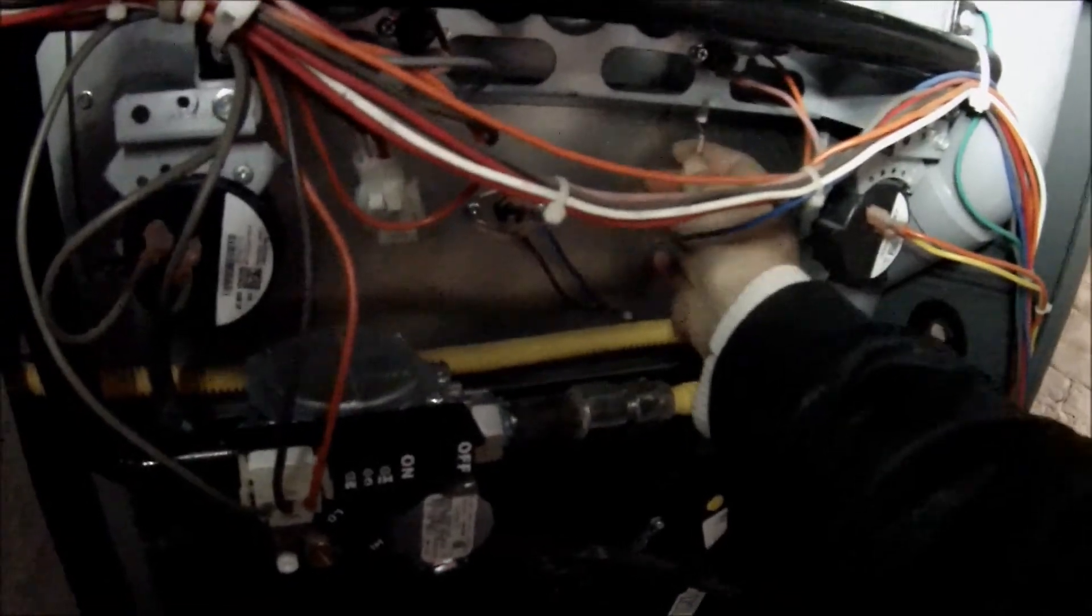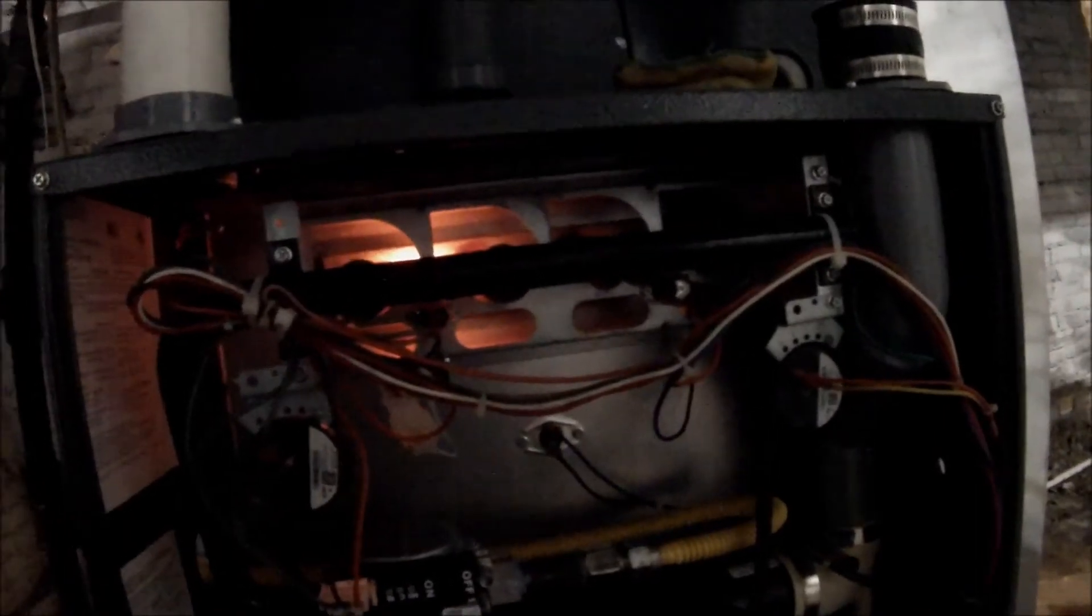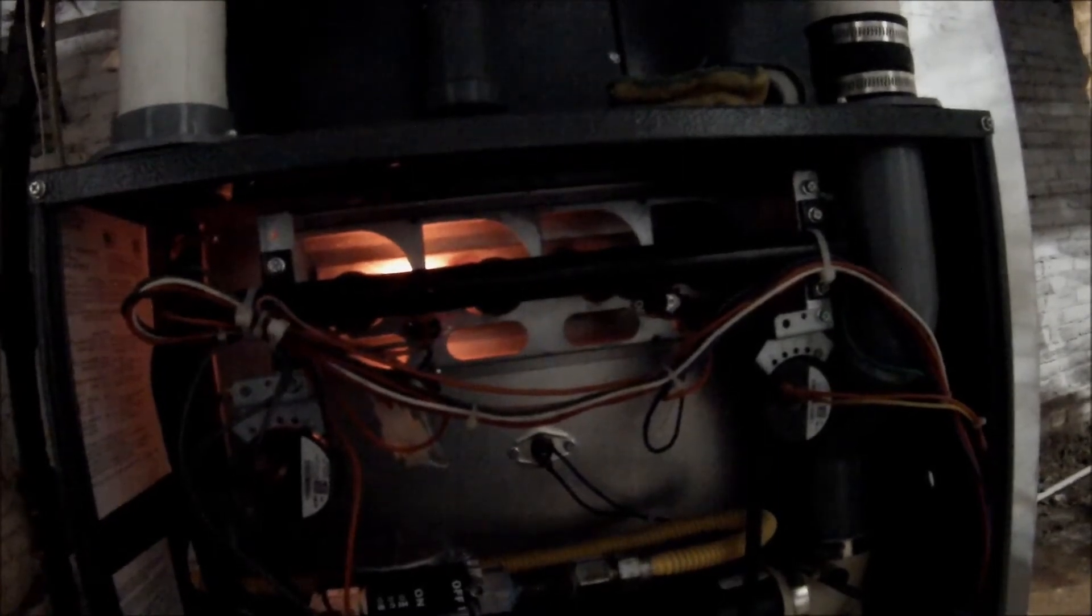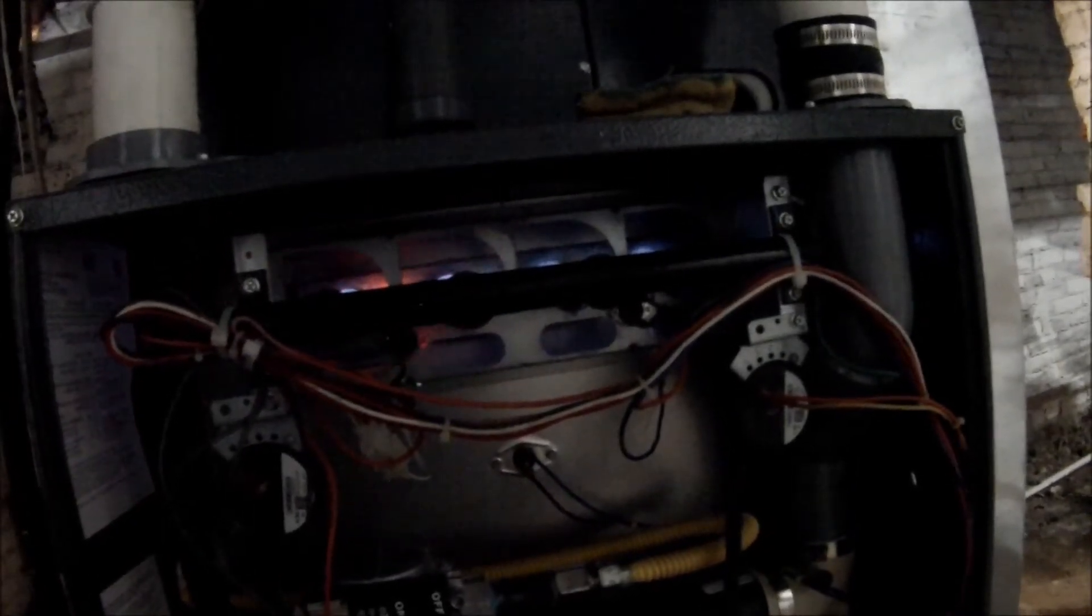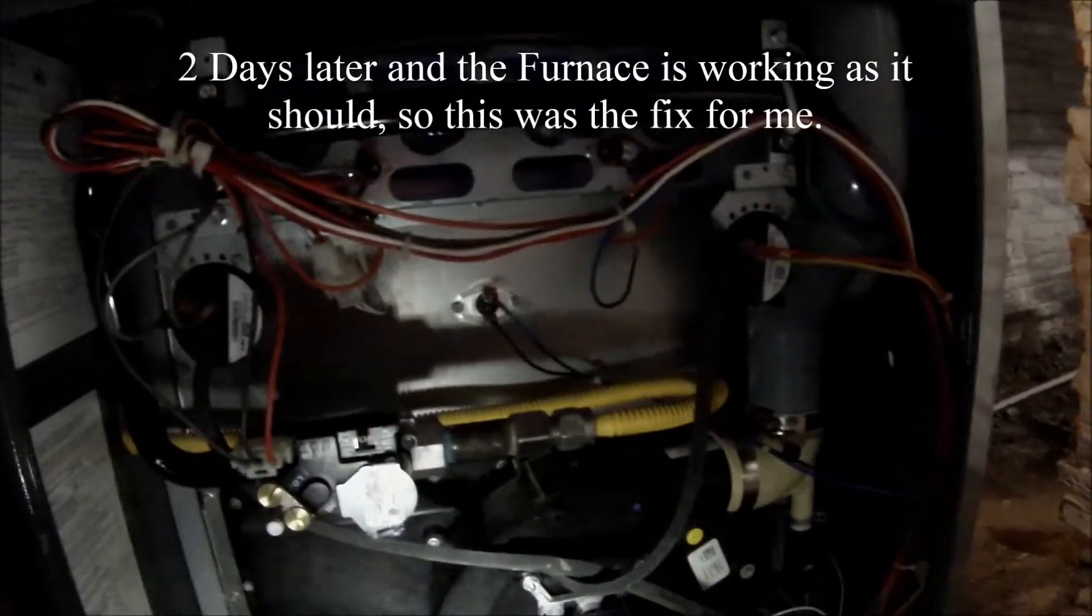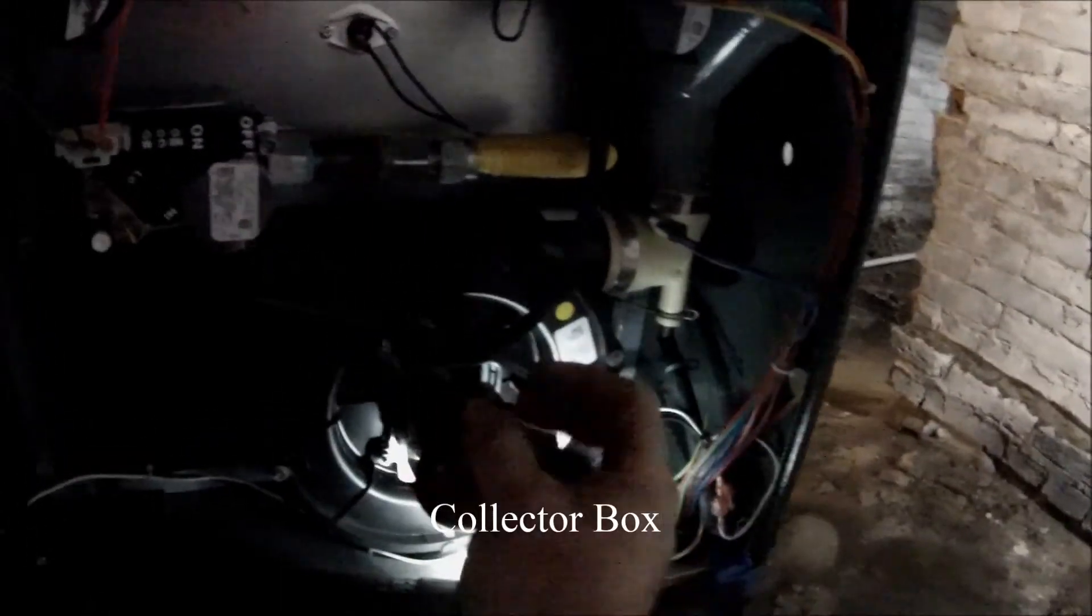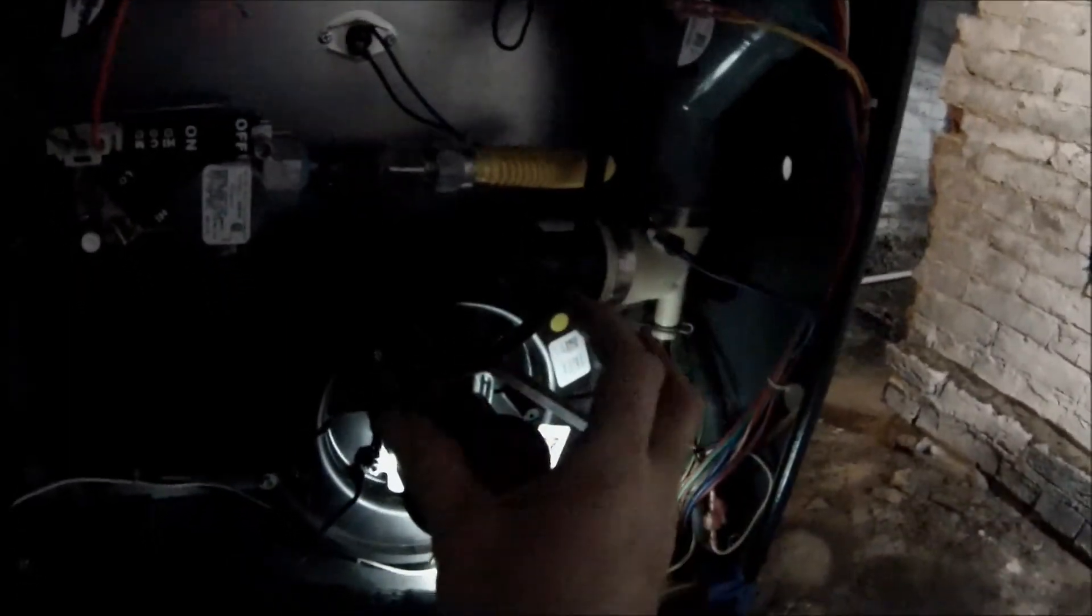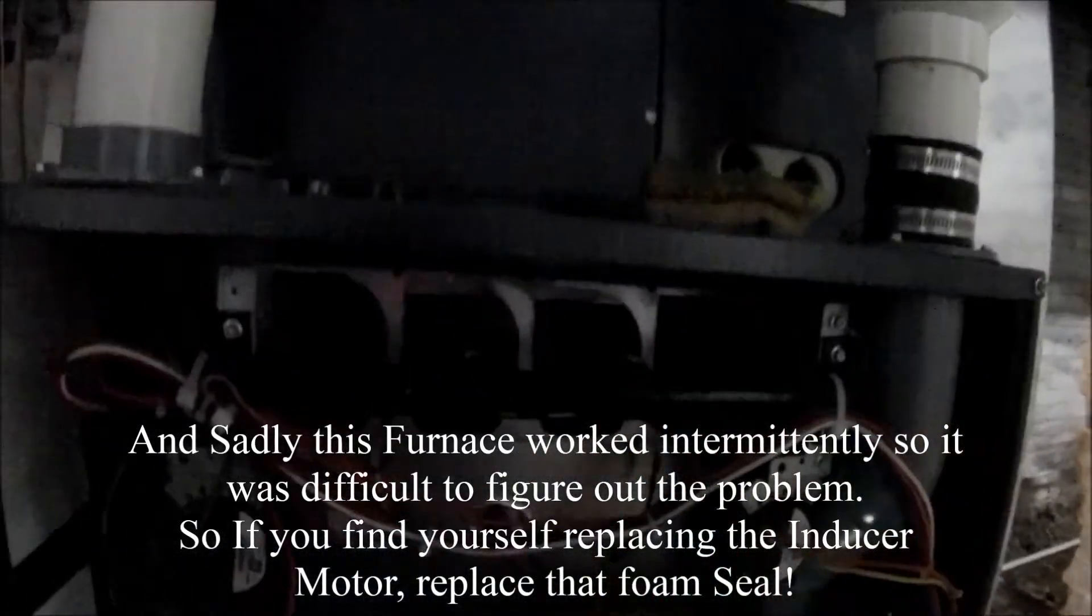So this should be good. Try that again. That, I just disconnected the sensor there. That's all that was. Alright, so hopefully that fixes the problem. Again, I thought it was the gas valve. Because I wasn't getting no error codes on this. No flashing on the control board. Saying that my pressure switch was bad or anything like that.